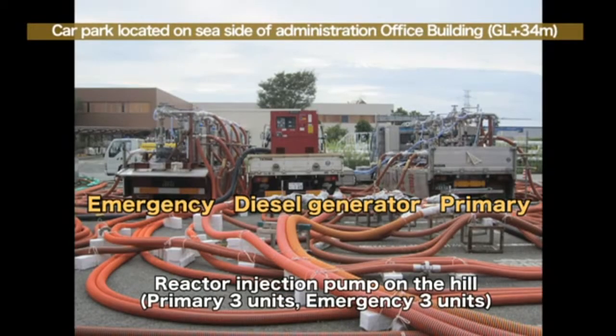The reactor injection pumps on the hill are arranged as shown on the screen. The 3 pumps for regular use are on the right side, with the power being supplied from a transmission line. The transmission line is connected to several transmission lines for increasing power supply reliability. The power supply to the pumps comes from Okuma number 2 line at present. However, in case of a blackout, the power supply will be maintained through the other 4 systems, such as the Okuma number 3 line, Tohoku nuclear line, Yonomori number 1 line, and so on. Furthermore, the pumps for emergency use are on the left, and a diesel generator is in the center. The power supply to the pumps for emergency use is maintained through the diesel generator.